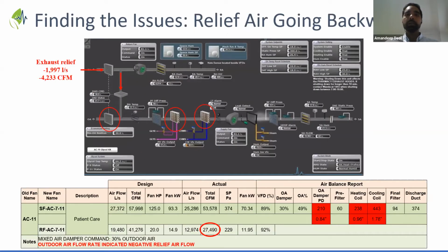The third example is another interesting one, where your return fan is not working as expected and the supply fan still needs to get all the air. So in this case, the supply fan was pulling the air through the exhaust relief. So basically, none of the air from the return system is exhausted. And in fact, the makeup air that's needed by the supply fan is being drawn through the exhaust relief. And you can see it's related, because your outside air damper in this scenario is again at a higher pressure drop, around 0.84 inches.